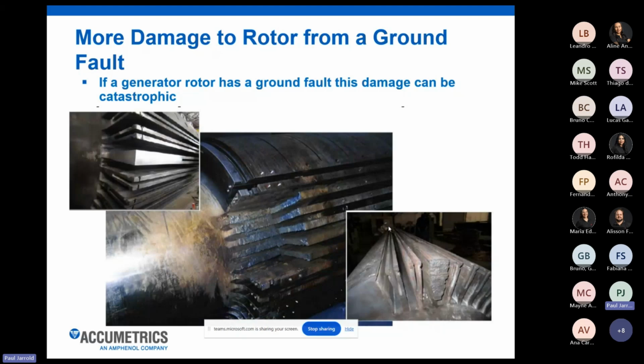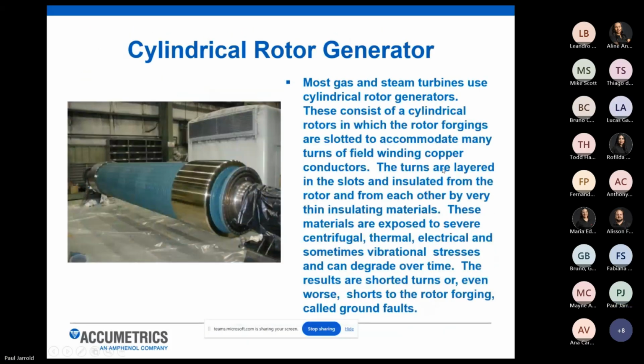So this is some more damage that's happened to customers' machines due to a catastrophic ground fault, where now the rotor has to be pulled out of the machine and all the windings have to be removed. In this case, the customer is able to cut and re-weld in some slots for those field windings, which is a massive cost to them.